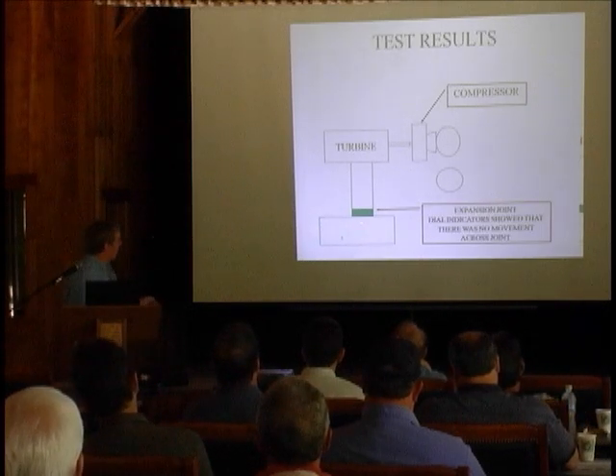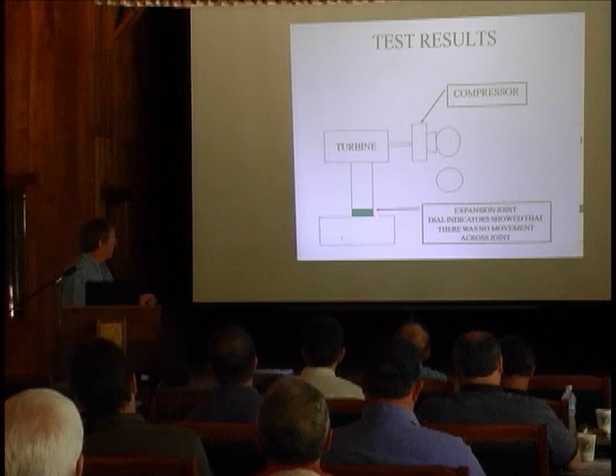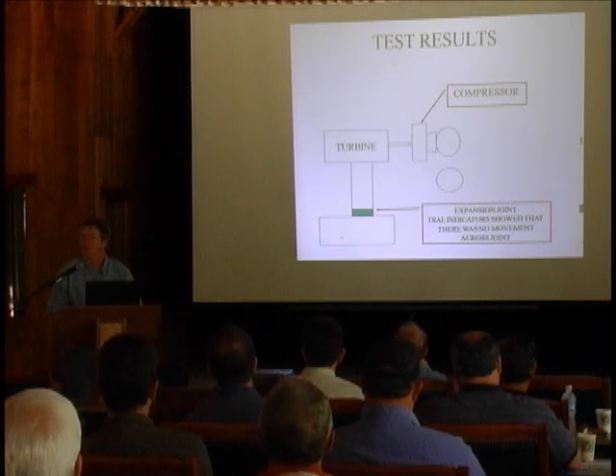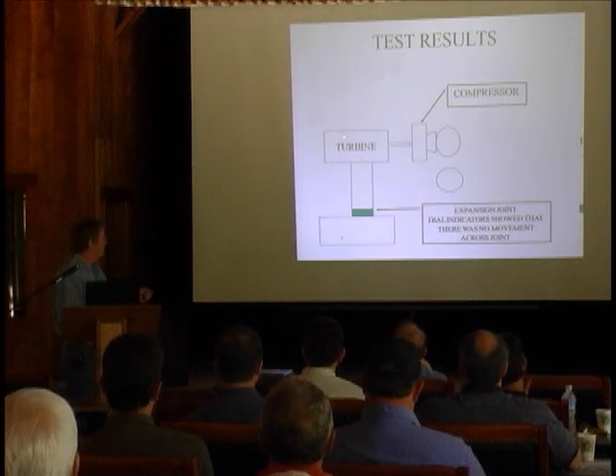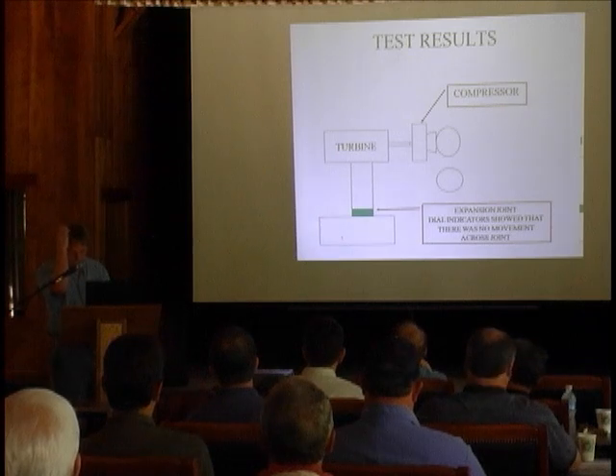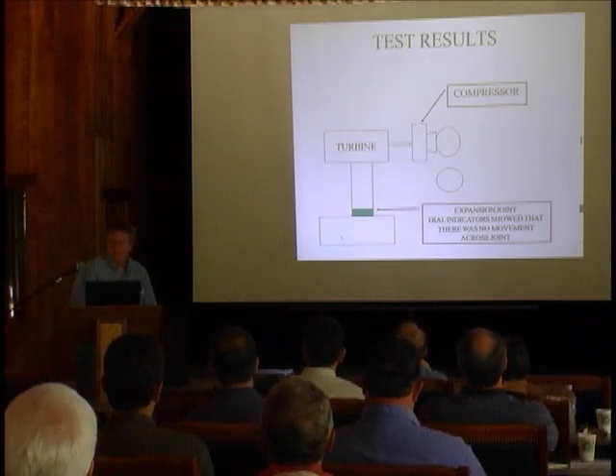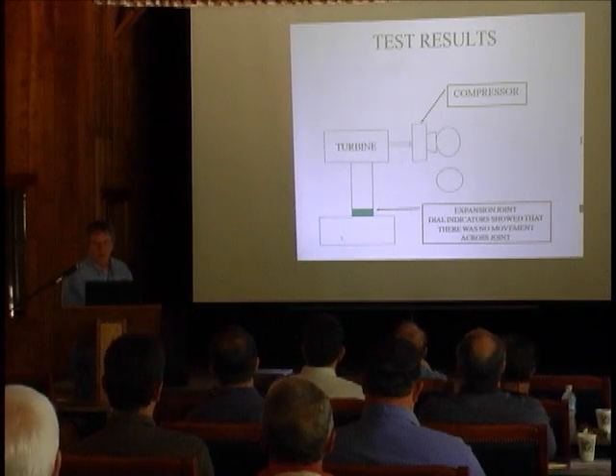So I put dial indicators across the expansion joint. I drew vacuum, absolutely positively no movement at all. This turbine was braced, and when you drew vacuum, it had no effect on it at all. So I go, oh boy, that's weird. So I said, well, if it's not moving, the compressor must be moving.